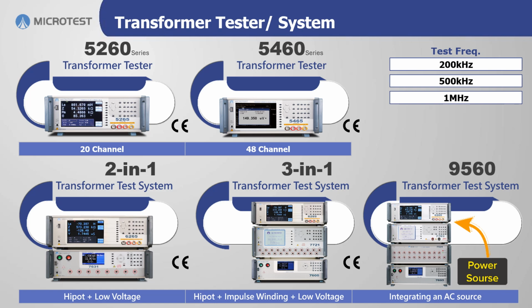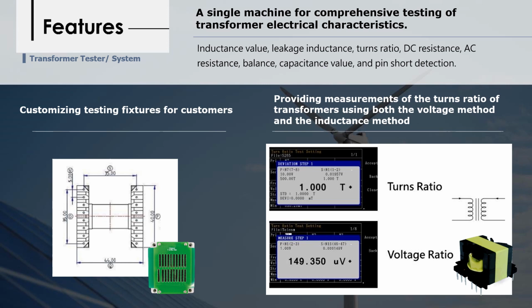Additionally, we have integrated transformer testing with high voltage, including the 2-in-1, 3-in-1, and 9560 series. In the 2-in-1 configuration, we have integrated transformer safety testing with low voltage, allowing simultaneous testing with hipot, insulation, and low voltage electrical properties. In the 3-in-1 configuration, besides safety hipot and low voltage testing, we have incorporated impulse winding testing, creating an all-in-one high and low voltage transformer test system. In the 9560 series, we've integrated an AC source into a 3-in-1 configuration, enabling dynamic testing of transformers. In addition to providing precise measuring instruments for transformer testing, Microtest offers customized fixture capability for different transformer products.